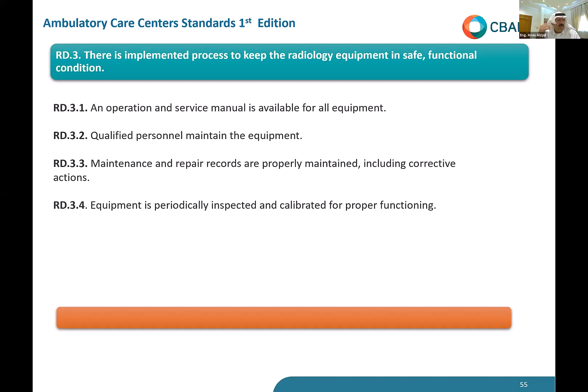The most important piece of equipment which needs calibration is the electrical safety analyzer. If you are a big center and the electrical safety analyzer is not calibrated, it means all the equipment in your center is not calibrated, because that's the one you use for calibration of everything. So please make sure the electrical analyzer calibration is done. All medical calibration, including the IVs and the pumps, if you have them, needs to be very well calibrated.